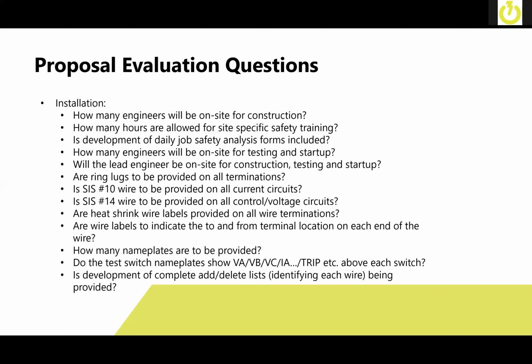Development of daily job safety analysis forms. Engineers on site for testing and startup, along with the lead engineer on site for construction, testing, and startup. A lot of times people may say they're sending an engineer out, but he may be someone that has no idea what's going on with the facility or with the retrofit to be performed. Are ring lugs provided on all terminations? Is SIS number 10 wire provided on all current circuits, or is it all SIS number 14 wire? Are heat shrink wire labels provided on all wire terminations, and do the wire labels indicate the to and from terminal locations on each end of the wire?